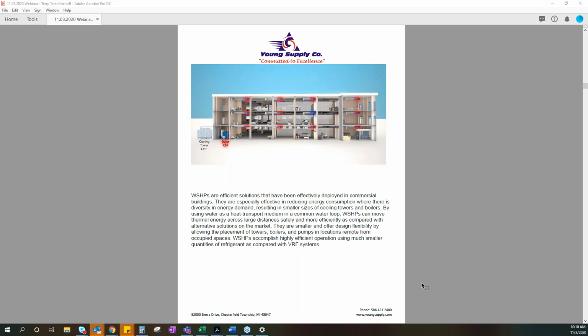Here's an option where we have a water source heat pump, and this is also very similar to what you're going to see in VRF. This is the heat recovery mode. Here we're using a water loop system. You can see the chiller and boiler in the bottom left. And if you look at the various heat pumps inside, you'll notice that some of them are in heating, some of them are in cooling.